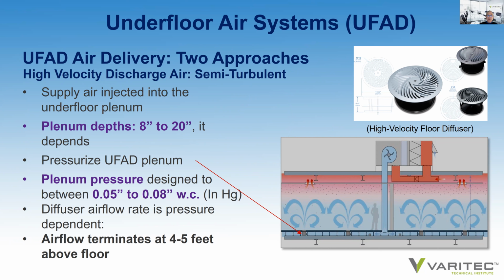The plenum pressure needs to be uniformly pressurized. That's another aspect to underfloor air systems. And I know our manufacturer, and I'm confident there might be others, our manufacturer will help lay out the duct injection points to effectively distribute the air to maintain a uniformity of plenum pressure throughout the plenum. And that is critical. When you're pressurizing a plenum to 0.05 to 0.08 inches, the airflow through the diffusers is pressure dependent. The amount of air out of a diffuser is dependent upon the pressure local to that diffuser. So if you have pressurization swings throughout the plenum, you're going to have swings in airflow out of the diffusers. But again, a properly designed system eliminates that concern about an unevenly pressurized plenum.